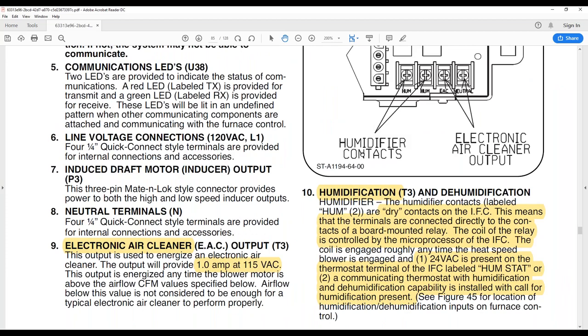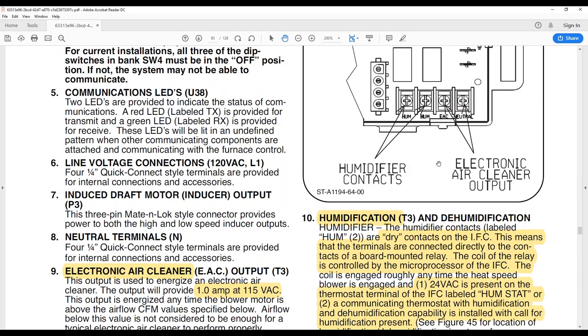One huge question we always get is about the electronic air cleaner and the humidification terminals. Okay. Main thing to know with the electronic air cleaner, the output, the two terminals on the electronic air cleaner, right here, marked EAC and neutral, those are 110 volt outputs. So the EAC will have 110 volt on it, and then neutral will be your 110 volt neutral. Okay, those are only energized depending on how big of a blower motor you have, but they only energize above 500 CFM. When you get to the larger blower motors, like a 3/4 horsepower or a 1 horsepower motor, they then energize at 600 and 700 CFM. So the minimum is 500 CFM on the standard 17-inch wide furnaces. That's when the EAC will energize these terminals.